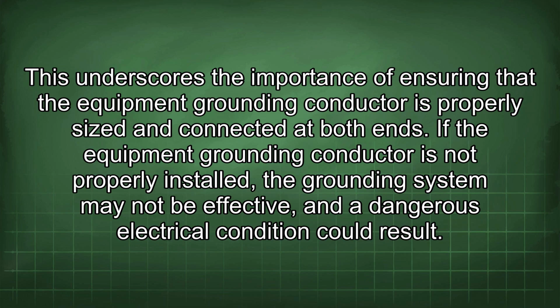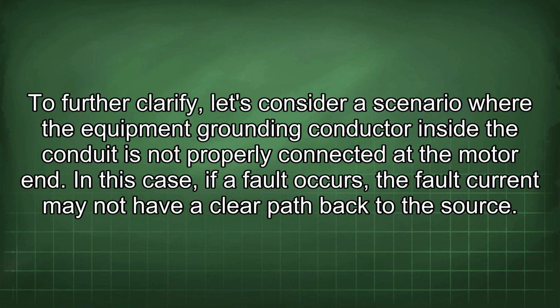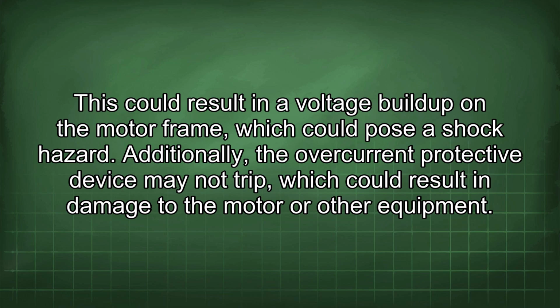If the equipment grounding conductor is not properly installed, the grounding system may not be effective, and a dangerous electrical condition could result. To further clarify, let's consider a scenario where the equipment grounding conductor inside the conduit is not properly connected at the motor end. In this case, if a fault occurs, the fault current may not have a clear path back to the source. This could result in a voltage buildup on the motor frame, which could pose a shock hazard. Additionally, the overcurrent protective device may not trip, which could result in damage to the motor or other equipment.